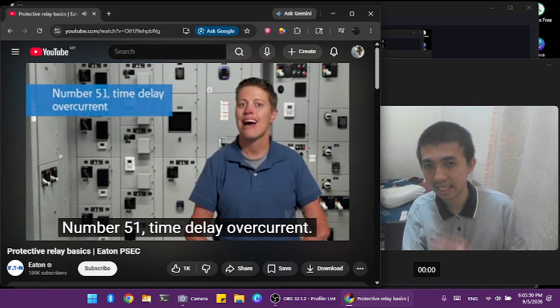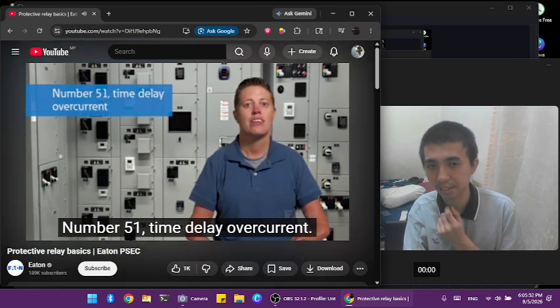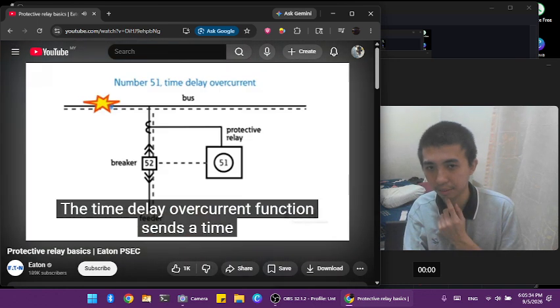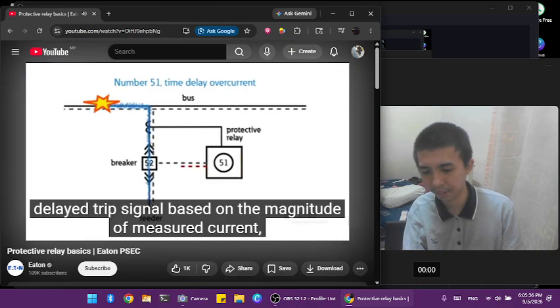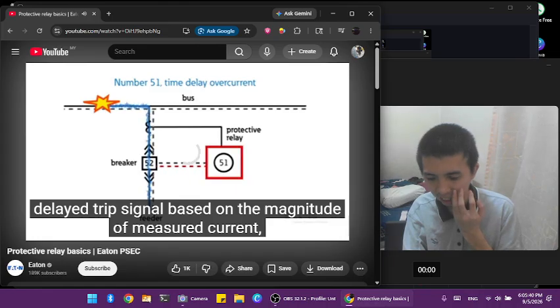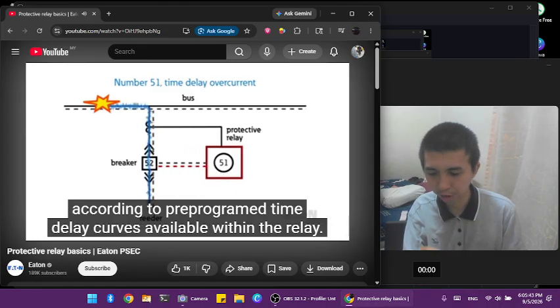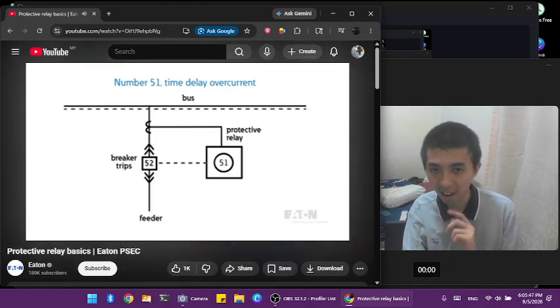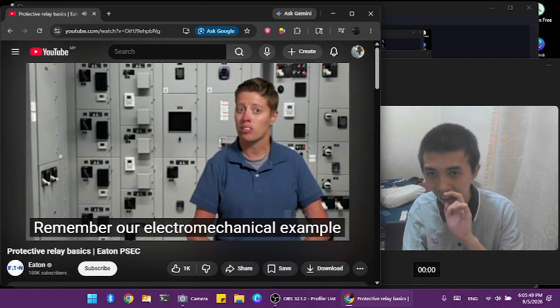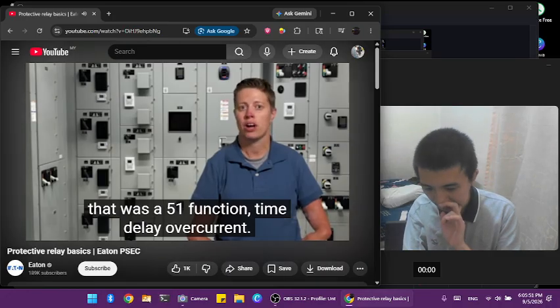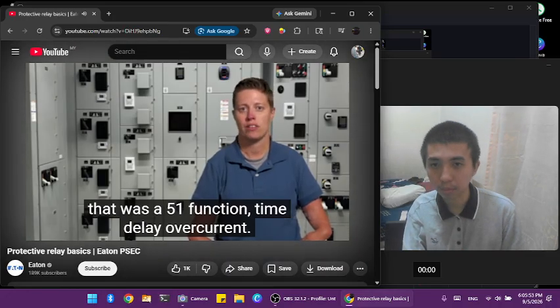Number 51, time delay overcurrent. The time delay overcurrent function sends a time-delayed trip signal based on the magnitude of measured current according to pre-programmed time delay curves available within the relay. Remember our electromechanical example? That was a 51 function, time delay overcurrent.